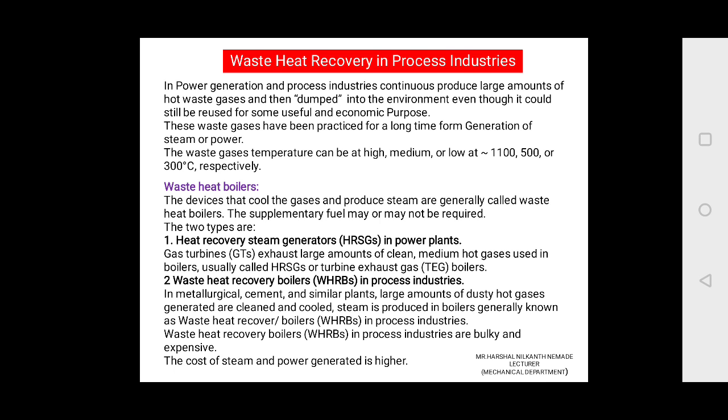Second, waste heat recovery boilers, WHRBs, in process industries. In metallurgy, cement and similar plants, large amounts of dusty hot gases are generated, and steam produced in a boiler from them is generally known as a waste heat recovery boiler, WHRB, in a process industry. Waste heat recovery boilers in the process industries are bulky and expensive. The cost of steam and the power generated is higher.